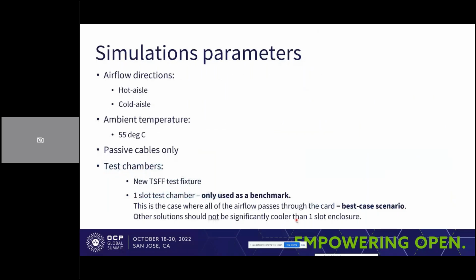What I simulated: I ran the simulation for both airflow directions, hot aisle and cold aisle, because both of them are really important. The ambient temperature was the same for both airflow directions, because what's really important here is the differences, not the absolute numbers. I used only passive cables to simplify my problem, so we will look only at the ASIC temperature.